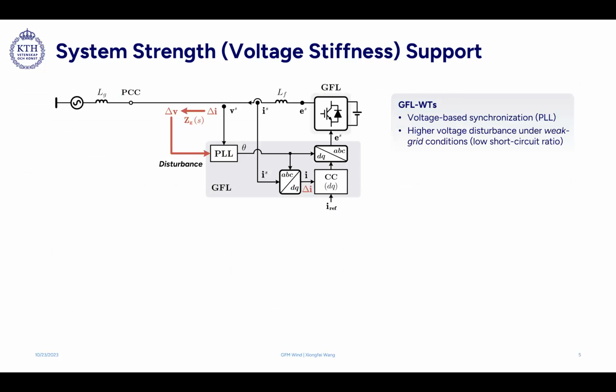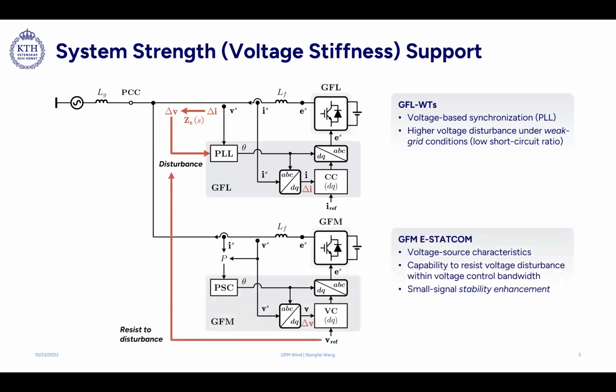To get a general idea about why this grid forming E-STATCOM can enhance the system performance, we show some basic control diagram. Here, this is the grid following wind turbines. They rely on the voltage measurement for synchronization. So whenever we have a much weaker grid, a small current disturbance can introduce a higher voltage disturbance. Then this voltage disturbance will go through the PLL and introduce some instability issues. But with grid forming E-STATCOM added, we can regulate the voltage measured by the grid following wind turbines. In this way, we can enhance the voltage stiffness. But this is just a general explanation.